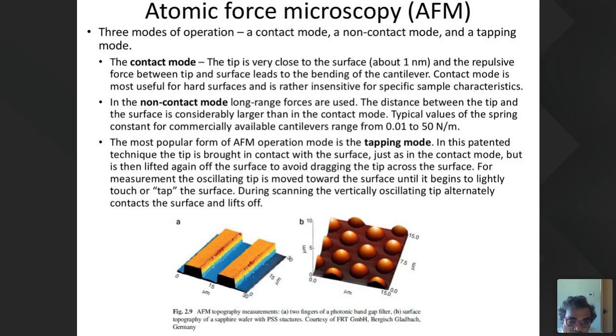In the non-contact mode, long-range forces are used. That means the distance between the tip and the surface is considerably larger than in contact mode. Typical values of spring constant for commercially available cantilevers are 0.01 to 50 N/m. The most popular form of operation is tapping mode. In this patented technique, the tip is brought in contact with the surface, just as in contact mode, but is then lifted, to avoid digging or dragging the tip across the surface.